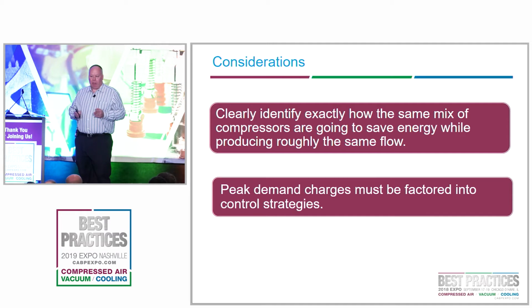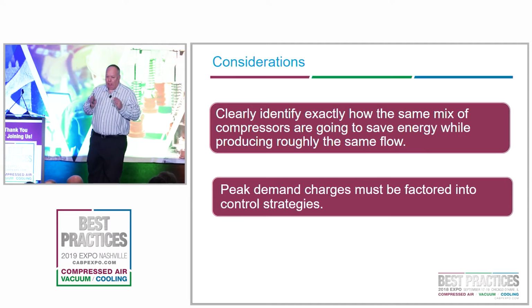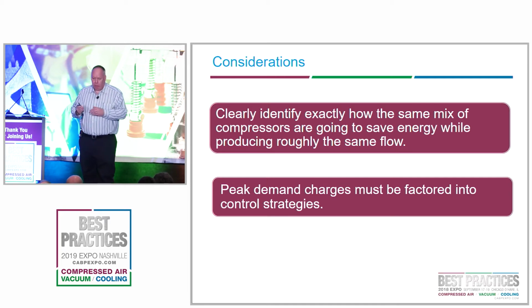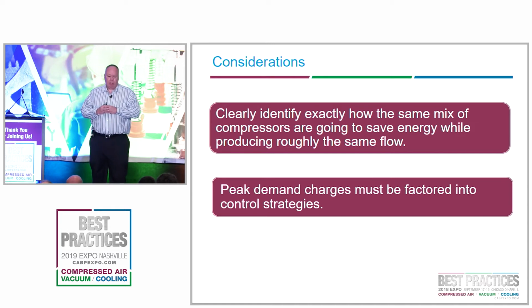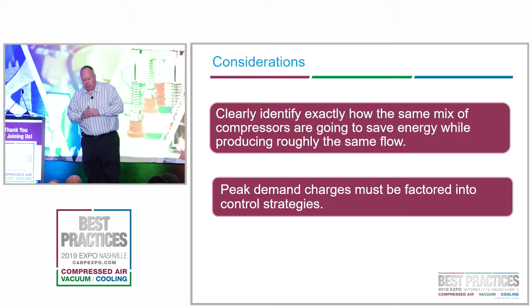If that integrator or controls engineer can't explain how their solution will make those 4 motors run less or consume less energy, you might want to double-check their numbers or find another resource to evaluate your system. Otherwise they're probably just reading off a brochure and spouting percentages they can't back up or justify, because every compressed air system is different, every plant is different. You can't paint a broad brush of energy savings without taking a deeper dive into the assets that are actually online.